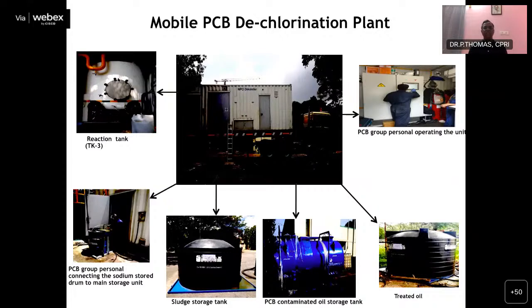Once the moisture has come down, we check the moisture content. Then we add the sodium dispersion. You can see the drum fitted into the van here, and there's another portion where we fit the sodium dispersion. Depending on the PCB level in the oil, say 50 ppm, 100 ppm, or 500 ppm, we calculate how much quantity of this sodium dispersion oil has to be added.